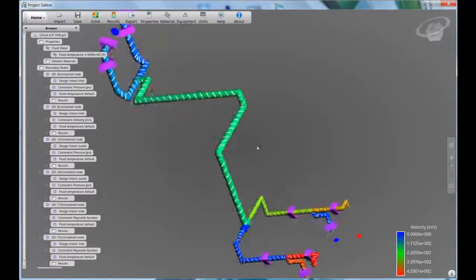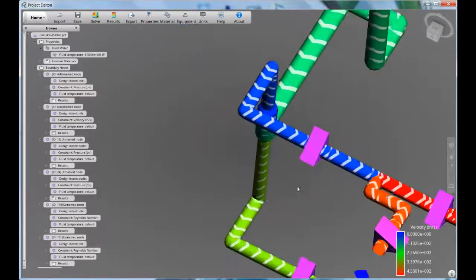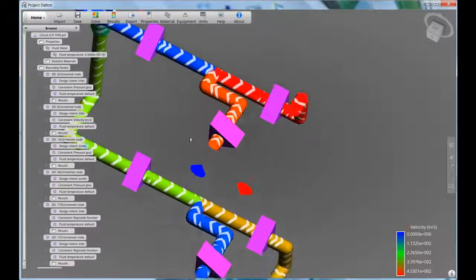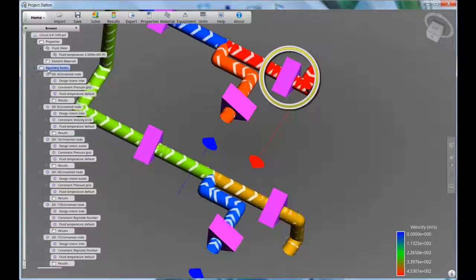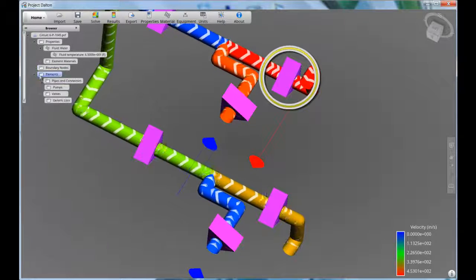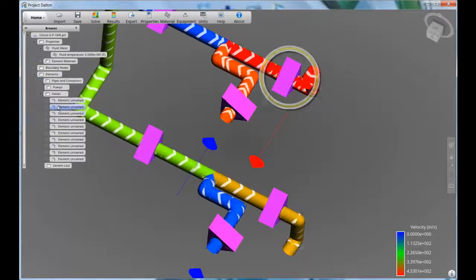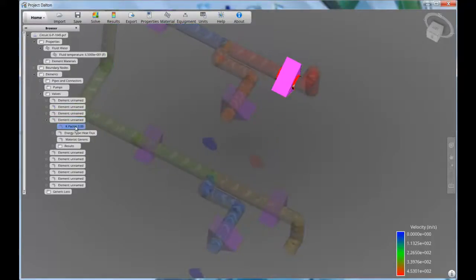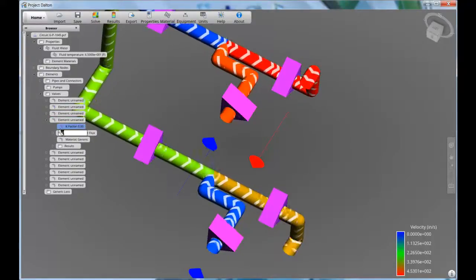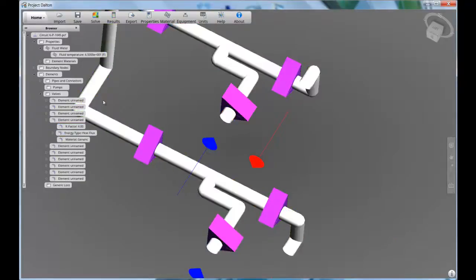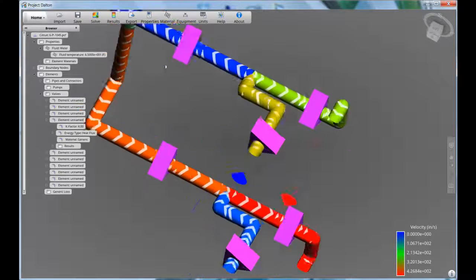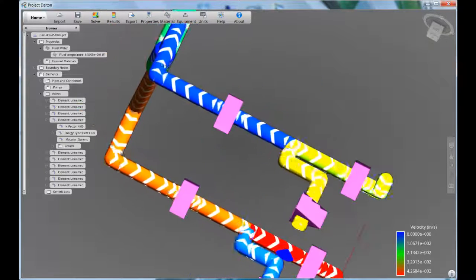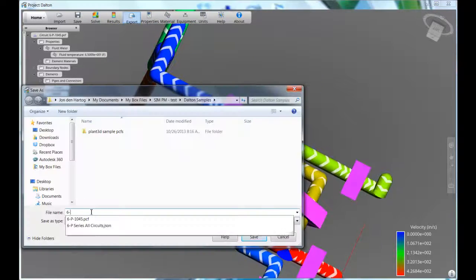Dalton also enables you to account for special components like pumps and valves. We'll zoom into this section of the model to see that we have a valve near an outlet that's fully open. We can go into that specific valve and modify the loss coefficient to see the effect of closing it a bit. We'll assign a loss coefficient of 4 to that valve, then recalculate. Now we see that we have less flow moving out of the model through this opening, and actually some flow in a nearby pipe has reversed direction.